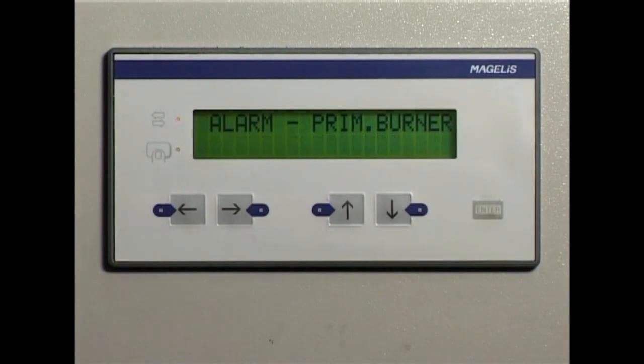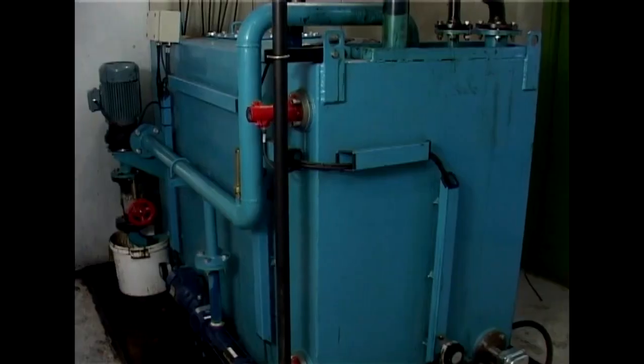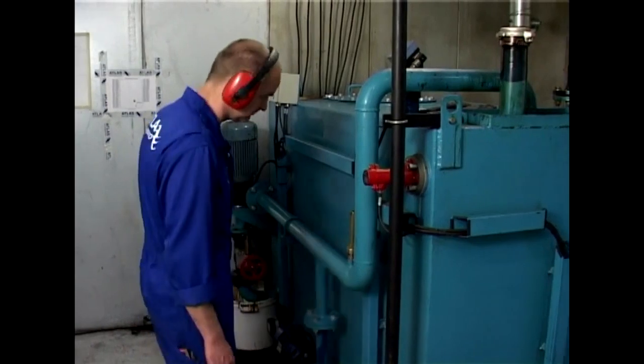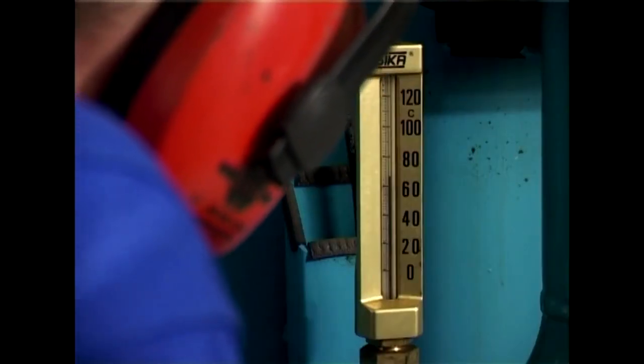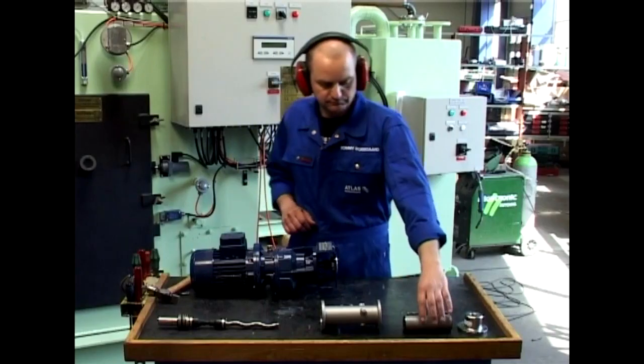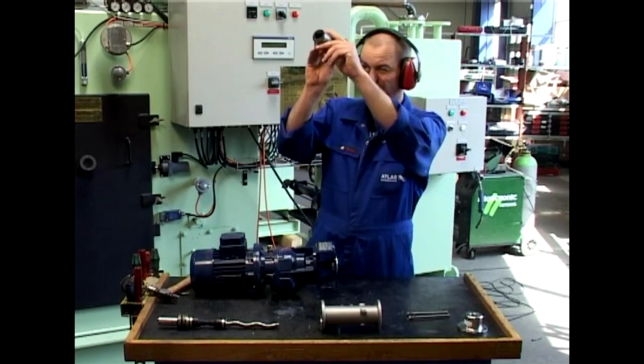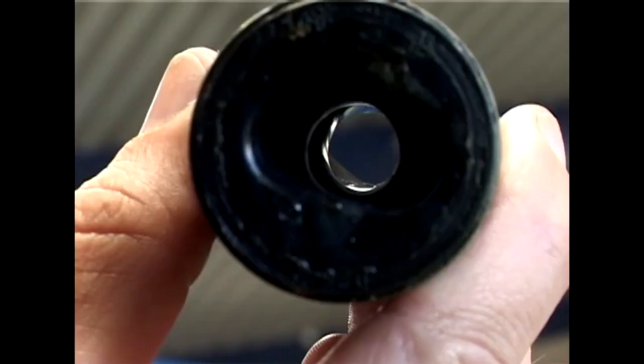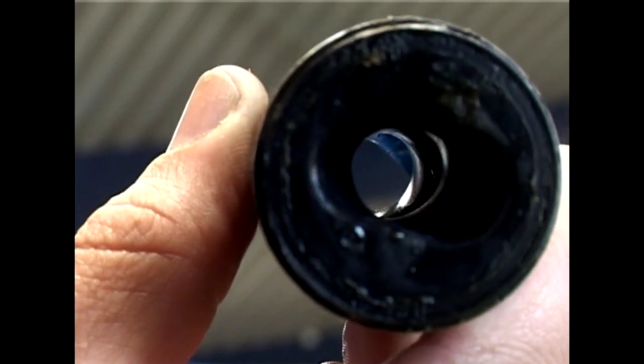If you have a flame failure on the sludge burner, check the temperature of the oil sludge. This has to be minimum around 60 to 70 degrees Celsius. Also, you must evaluate whether the sludge circulation pump and sludge dosing pump stators are worn and need replacement.